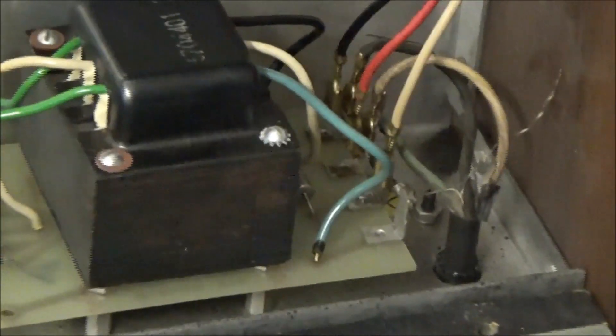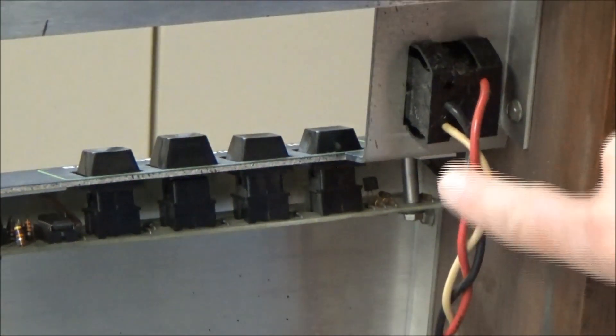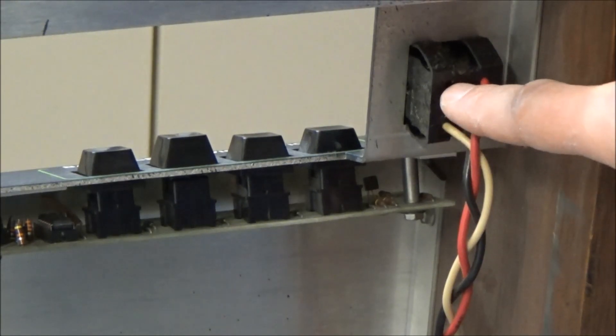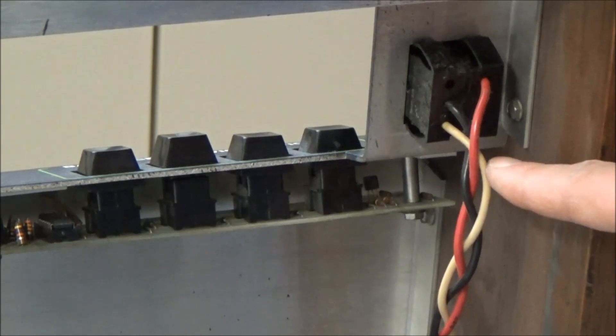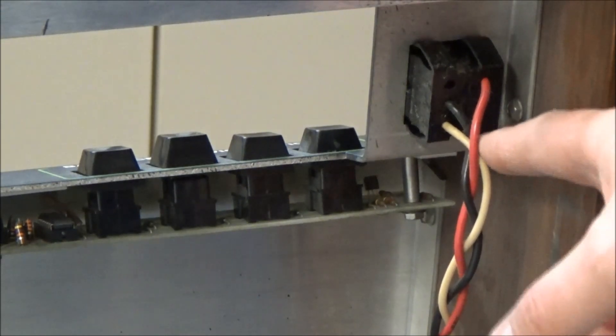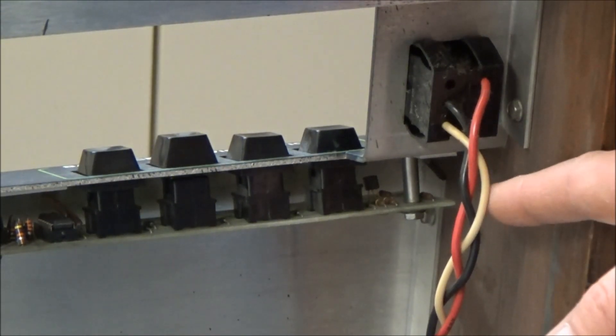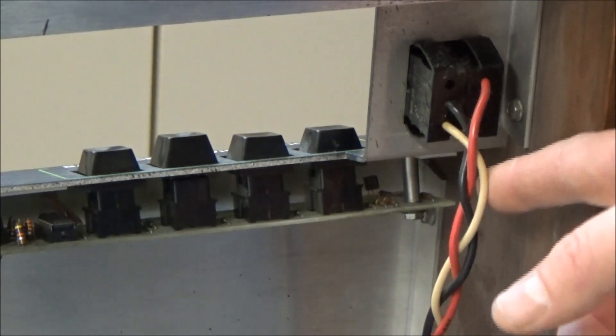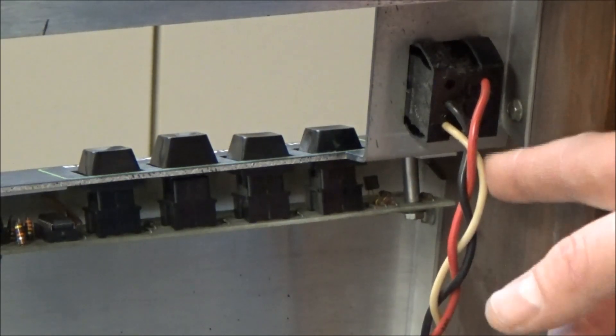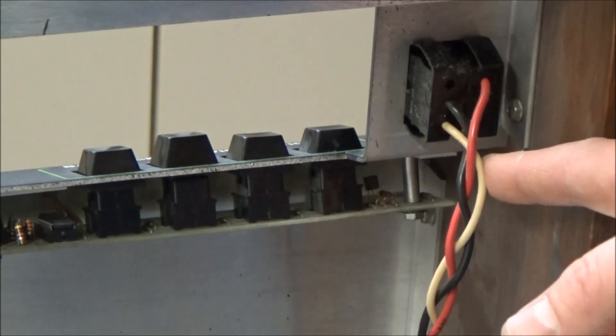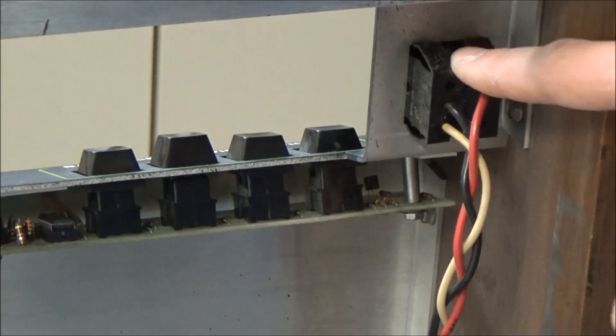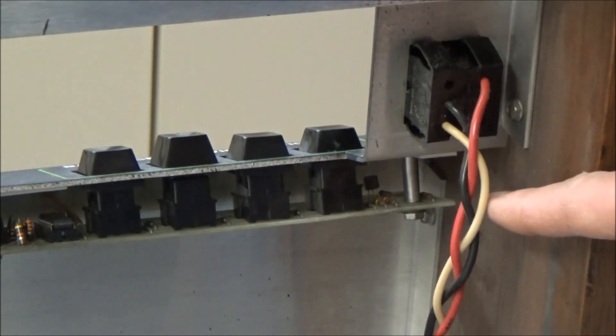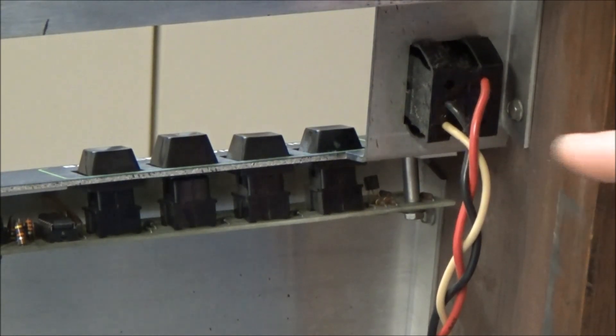the black wire comes into the power switch. And this switch is just a mechanical switch and unfortunately the other side of the wire coming out of the switch is white, which is confusing because white is typically reserved for the neutral wire. And when this switch is turned on we have a hot wire that's colored white. And that could make someone's day very, very bad.